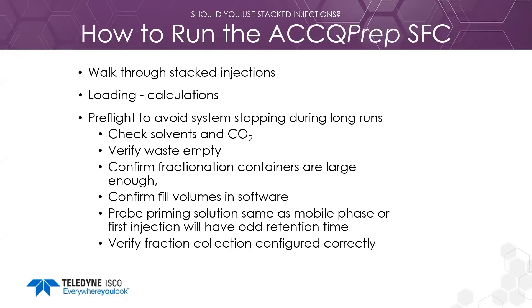Later in this presentation we will walk through the procedure for stacked injections. Once we have the resolution we need, we can do calculations to estimate the sample load. Since stacked injections can run over several hours, check that you have enough co-solvent and carbon dioxide, make sure the waste container is empty, verify that fraction containers are large enough, and make sure the container size is entered when starting the purification. Use the same solvent to prime the injection probe as you will use for the mobile phase, and make sure fraction collection is configured correctly.